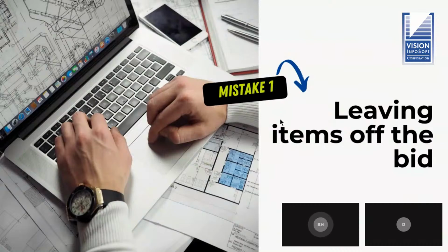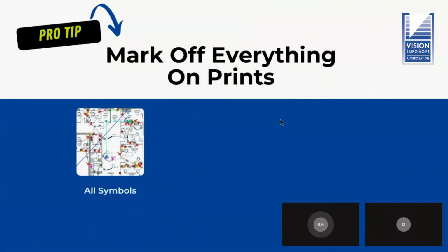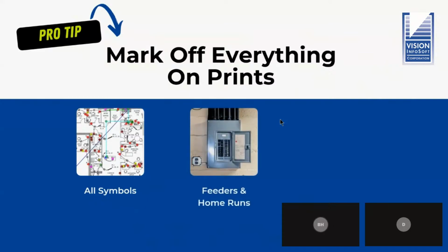Now, there's a few ways to avoid that. And the simplest thing is to mark everything off the prints, whether you're doing it manually as you mark it off the drawings and put it into your program or into a spreadsheet, however you're doing it. You have to mark it off the drawings. If you don't do that, you've opened up a big hole to miss things. So you want to mark off all the symbols, whether it's a receptacle or a light fixture. You want to mark off all the feeders and home runs. So you want to mark off where you started the feeder from and where it ended up. Same thing with the home runs. You want to mark those off in the drawings.